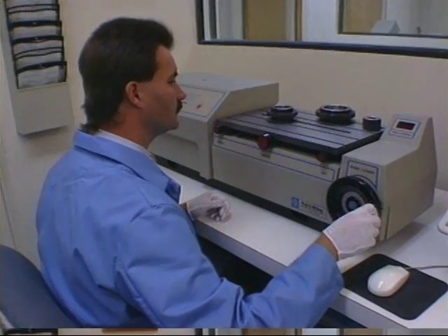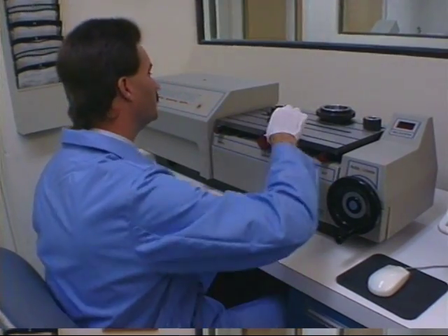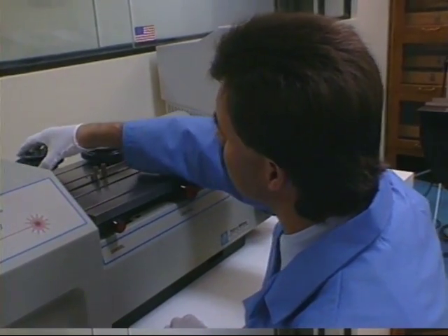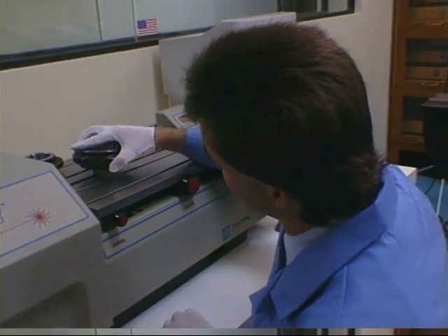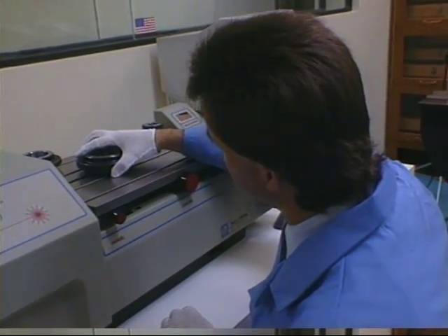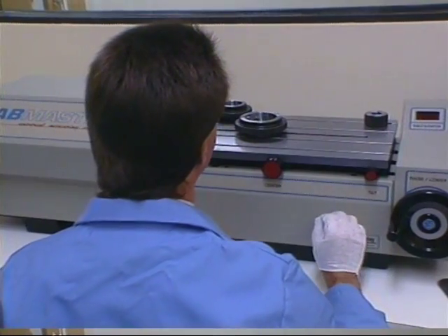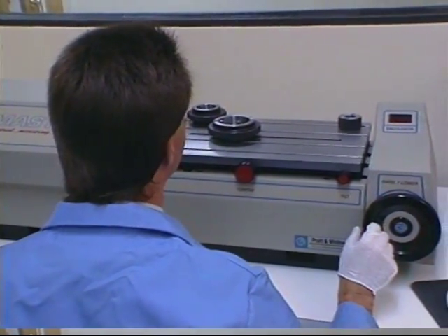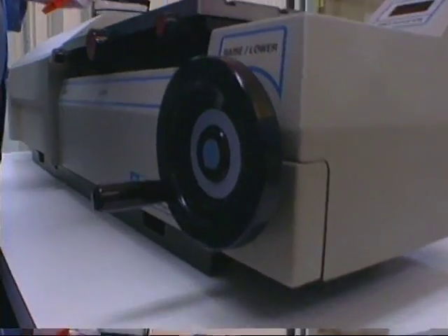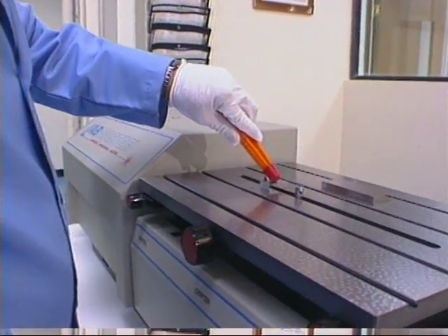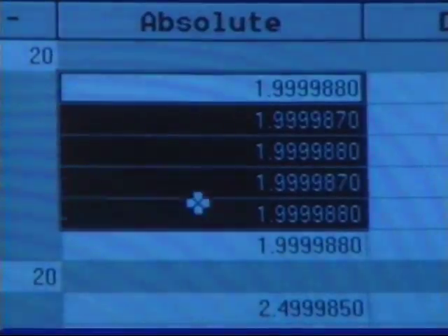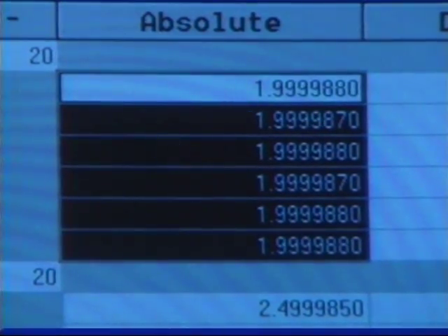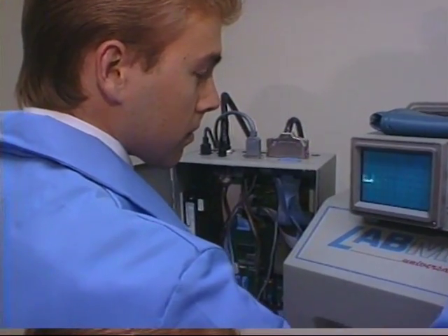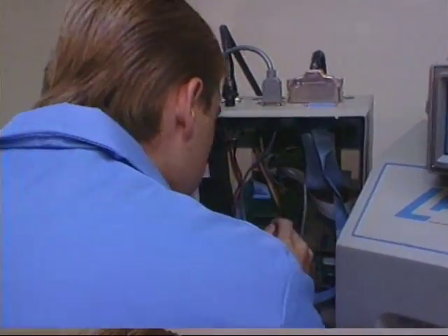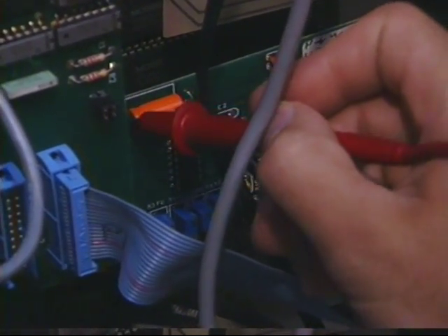With the LabMaster Universal Measuring System, a calibration lab can control the calibration of all production gauges and meet increasingly stringent supplier standards, such as Mil Standard 45662A and ISO 9000. LabMaster, a turnkey calibration system that delivers the accuracy of a comparator while offering the productivity associated with direct reading instruments, all built with serviceability in mind. In fact, the modular design facilitates problem isolation and field interchangeability.